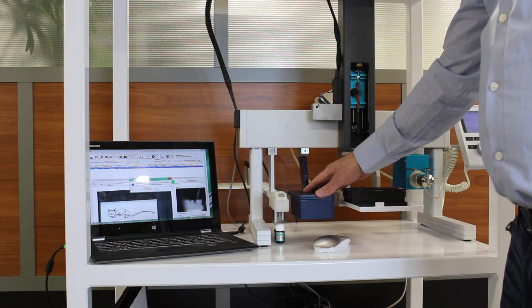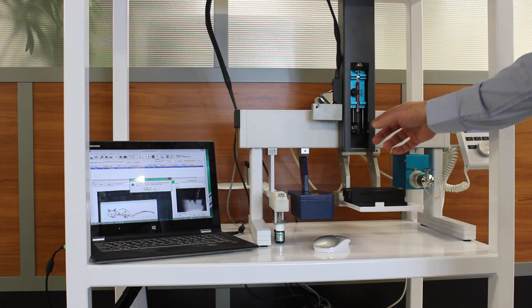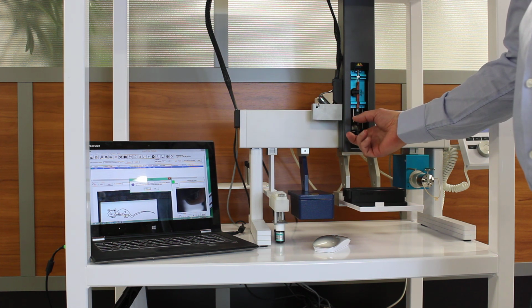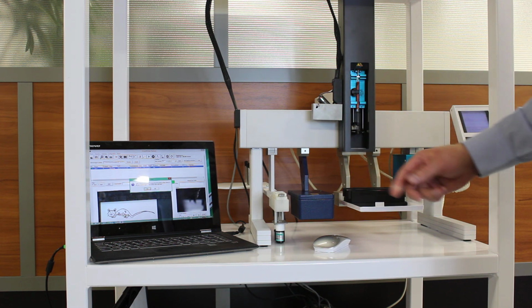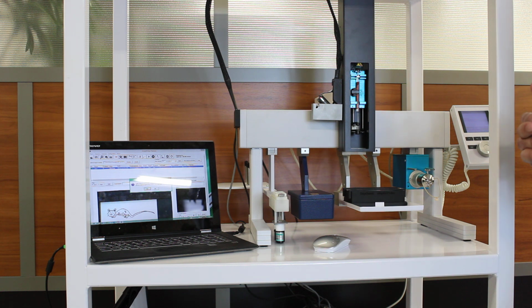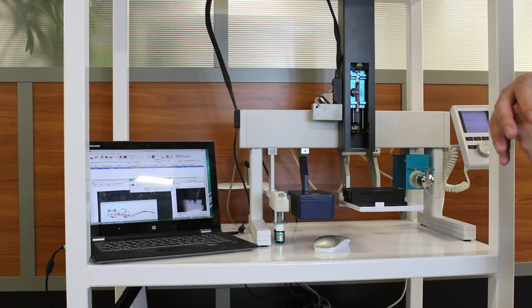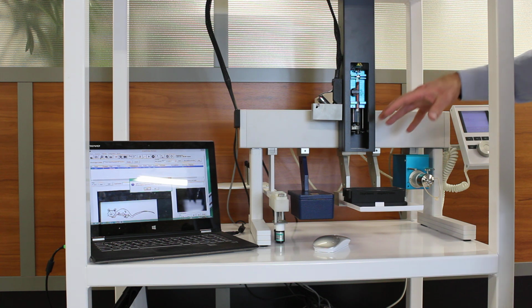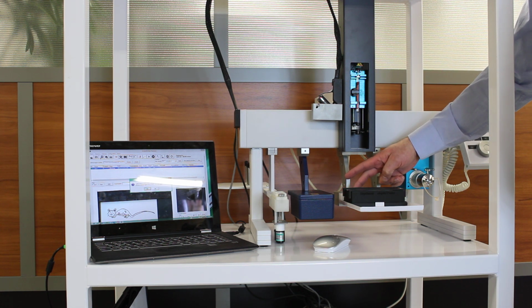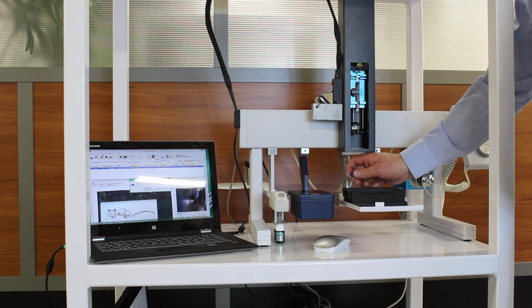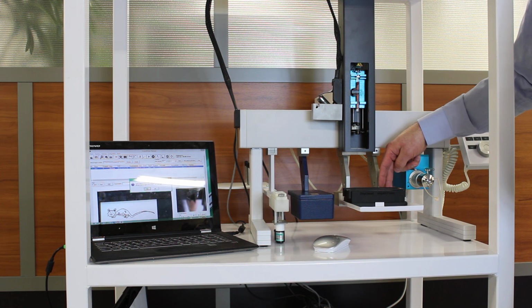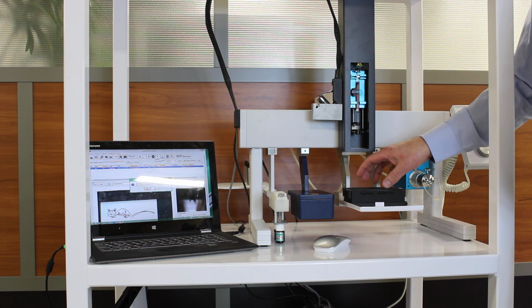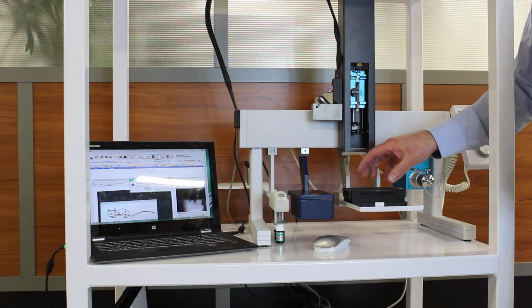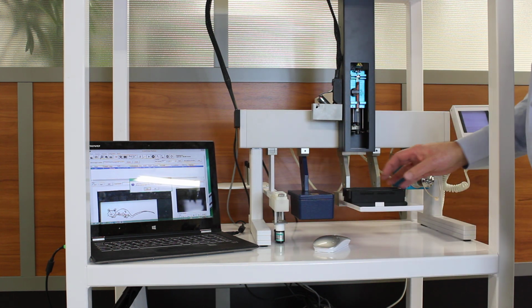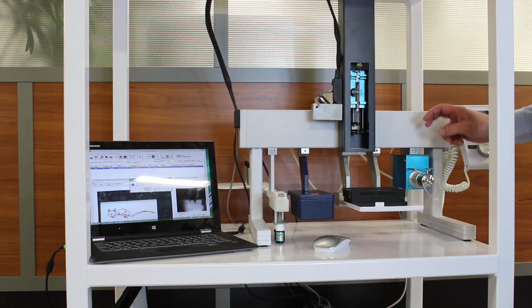We have a calibration device. Essentially, this calibration device gives us an offset from the laser down to the syringe tip, the needle tip. The camera is used for confirmation on the deposition of the droplet and then aspirating back into the syringe. We got a tray holder, consisting of standard holders in the back for 2 ml vials. Those are 7 different positions back here. Then we have 2 different trays for either mouse or whole body rats as an option, or a standard LC plate.